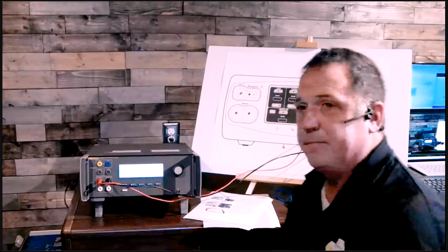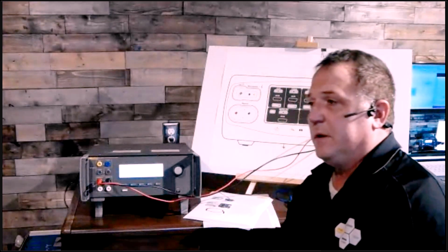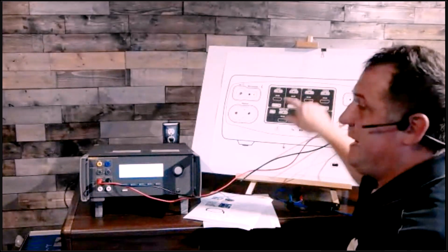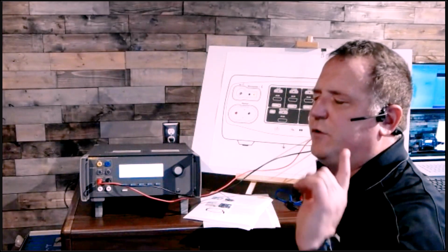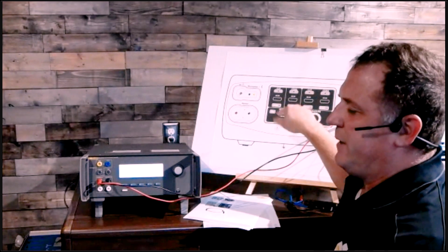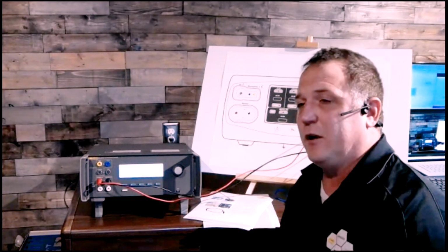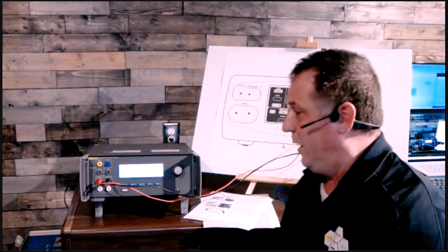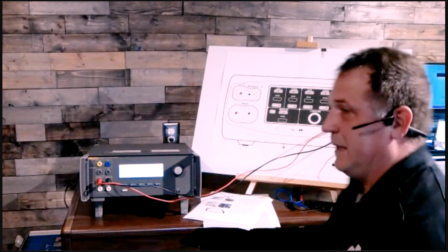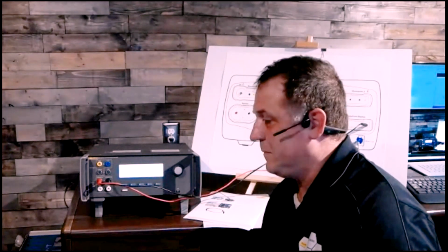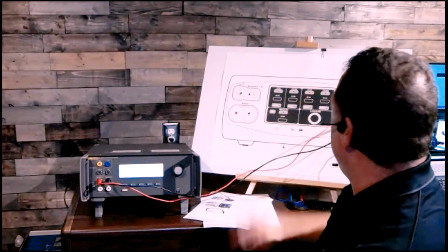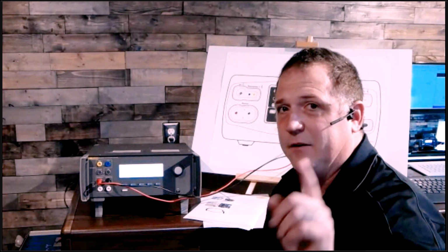I'll go ahead and hit stop so the fan shuts off, then I have to deactivate on my ESU. Don't forget to deactivate your ESU. Then I'll go to the next setting. So that's ligature - nice and simple, just about as easy as bipolar, but you had to go into service mode. Now we're in service mode.